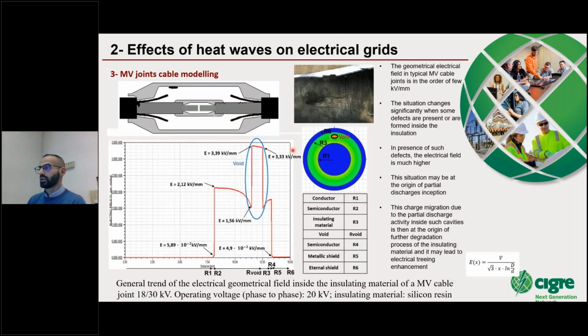In fact, it is possible that in the interfacial region between these overlapping insulating materials, some imperfection could be introduced, for example during packaging on site. We studied the electrical field along the insulating material, and we can say that the geometrical electrical field in typical medium voltage insulating material is in the order of a few kilovolts per millimeter.